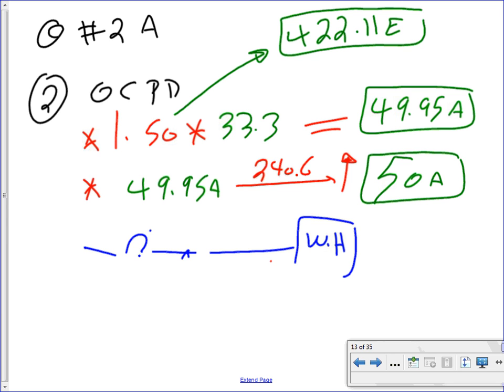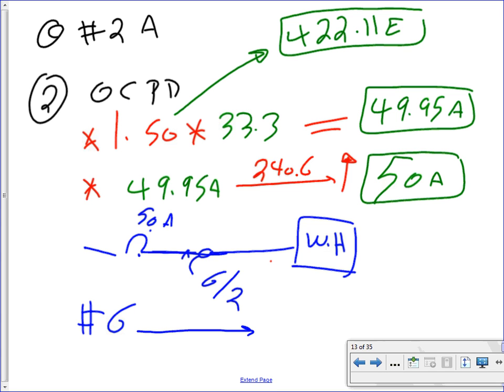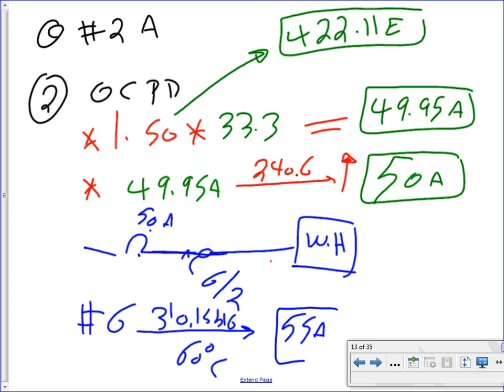Then what you need to do, ladies and gentlemen, here's my 50 amp circuit breaker. My conductor here is 6-2. My water heater, here's my water heater. And do me a favor, after you finish this, you need to go check how much amp can number 6 carry? 310.15(B)(16) under the 60-degree column. How much current can number 6 carry? 55 amps. 55 amps. So I'm good to go. Can you guys see that? That's the check. This is to check.